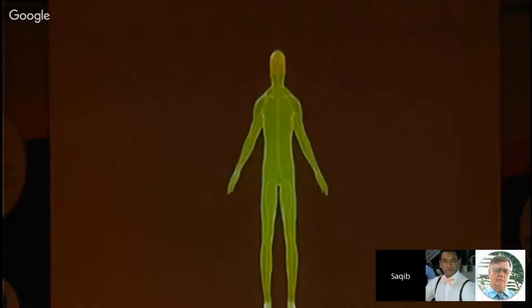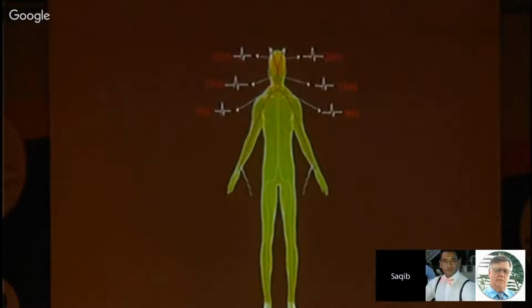What happens in sensories? I'm telling you this because a lot of people do not have an idea what happens. In sensories, you're stimulating peripherally. You can stimulate the median nerve, radial nerve, ulnar nerve, anything, and you send the signals up. As you know, sensories are ascending. You're monitoring the dorsal columns, and as the signals reach these parts, you monitor those waves. Now imagine surgery on the cervical spine. You would expect this brachial plexus wave at 9 milliseconds to be okay, but this wave may be delayed at 13, and this wave at 20 may be delayed. This is how you interpret. This is how you tell the surgeon that you're having changes. How do you do that? Your baseline is your control. You're not talking about data available online. Whatever baseline you have in that patient before incision is your baseline, and you want to see what happens during the surgery. Similarly, I hope you understand the upper limb.